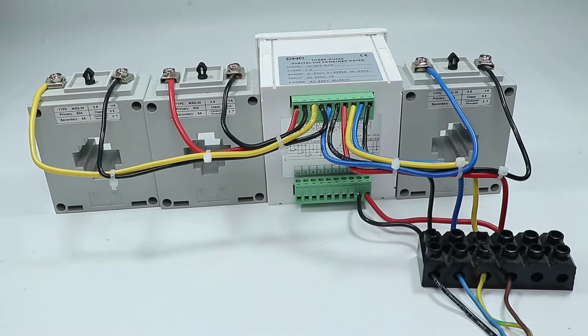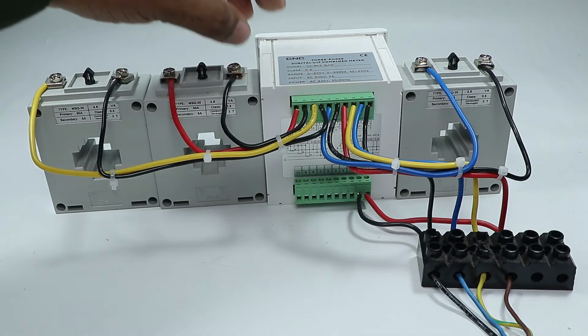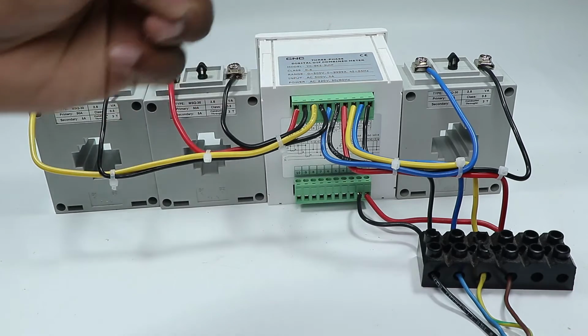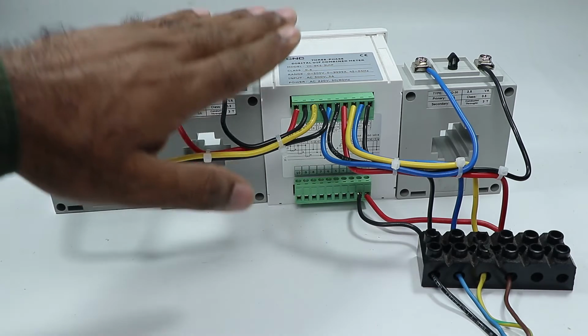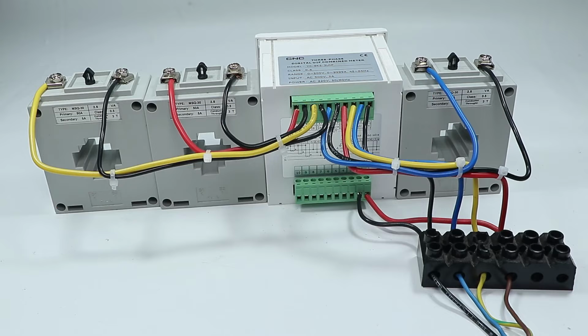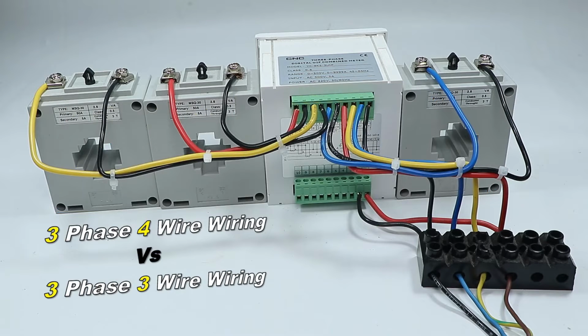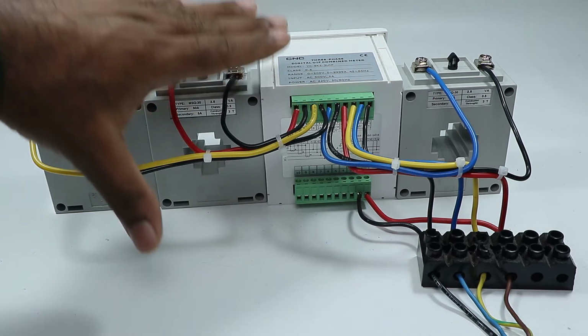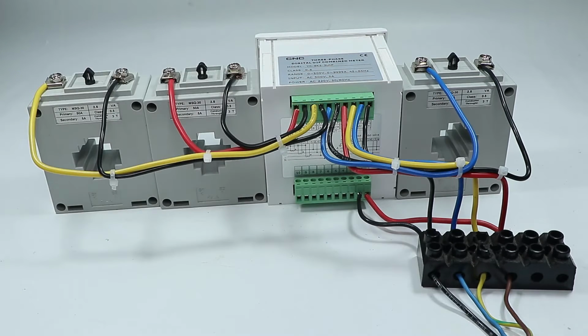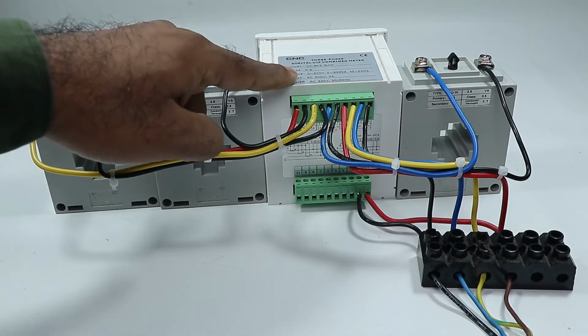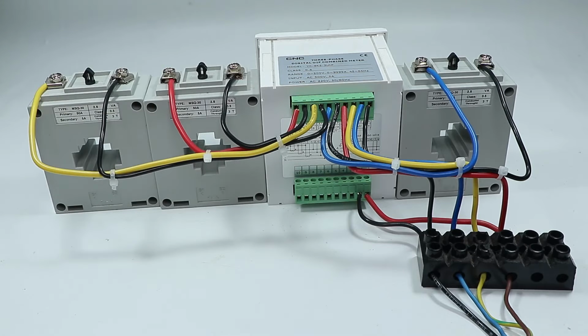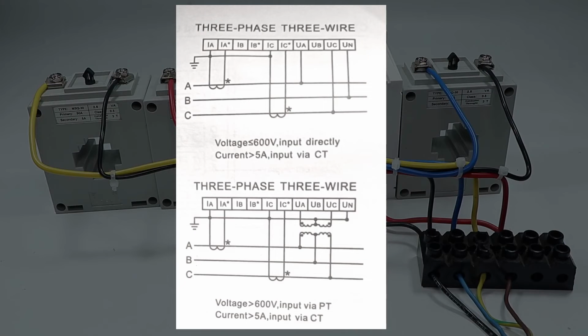Before explaining the wiring, I want to tell you that for this multifunctional meter, you can do the wiring in two ways. The first type is 3-phase 4-wire wiring, and the second type is 3-phase 3-wire wiring. What is the difference between these two? If you use 3 CTs with this meter, it is known as 3-phase 4-wire wiring. If you use only 2 CTs, it is known as 3-phase 3-wire wiring. This diagram you see on screen is of 3-phase 3-wire wiring.